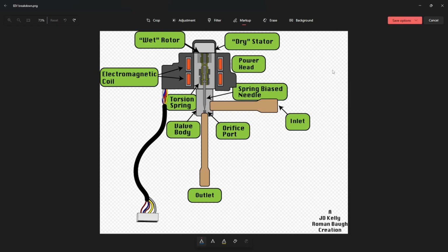The second test for these stepper motors is a resistance check. So the EEVs across the industry come in either 5-wire or 6-wire variants. With a 5-wire variant, you will only have one common. Just like any other low voltage circuit, because that's what this stepper motor is, a low voltage DC circuit in most applications, usually about 12 volts DC, you will only have one common wire on 5-wire.